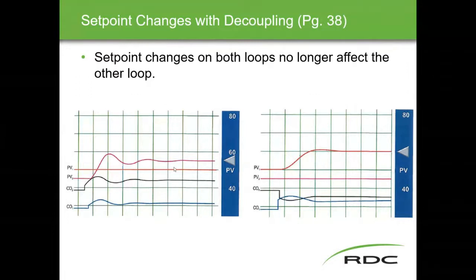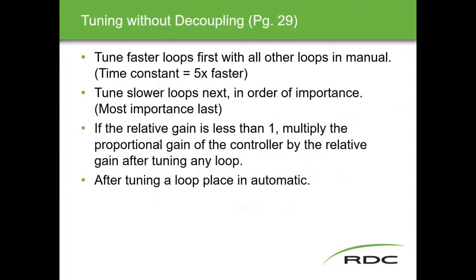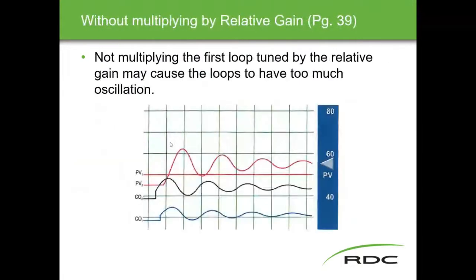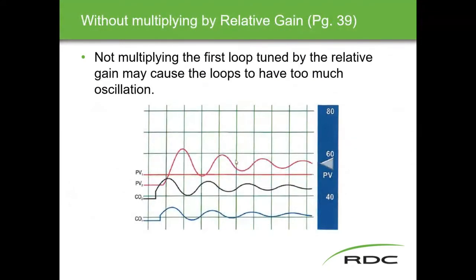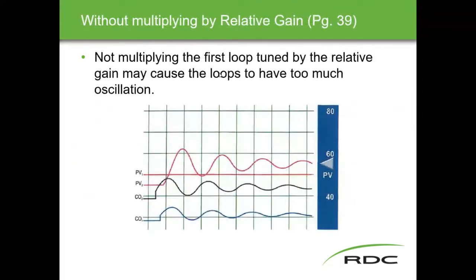Both decoupled responses are acceptable depending on process conditions — one is roughly quarter-amplitude, the other more critically damped or overdamped. What's not acceptable is when the relative gain is less than one and you don't multiply the proportional gain. A change in controller two with too aggressive a gain produces process oscillations in the PV. If you multiply by the other relative gain it reduces this value and gets you closer to an acceptable response.